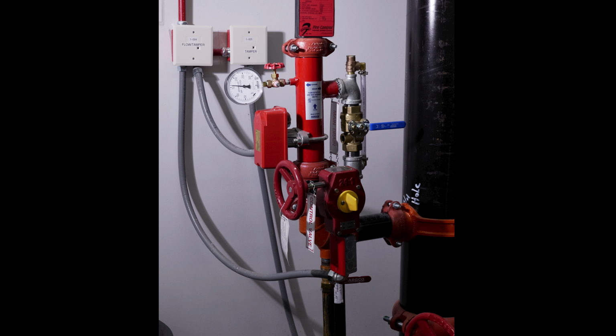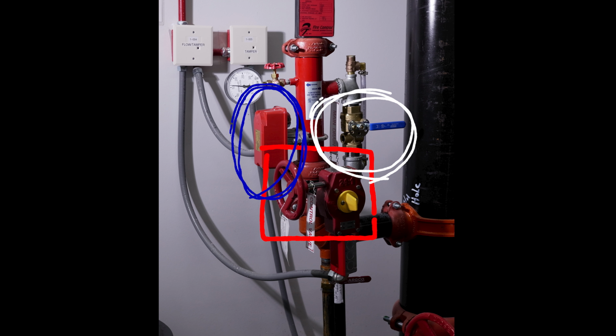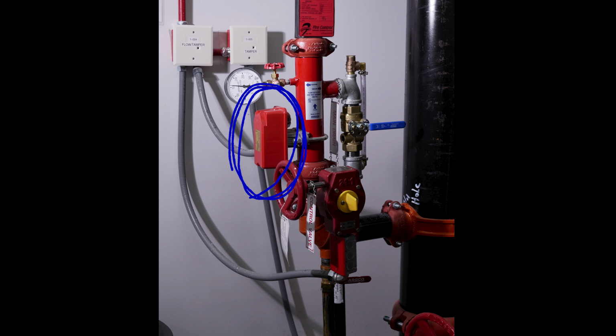The riser for this system is the simplest type, consisting of a main control valve, a combination main drain inspector's test valve, and a water flow switch to sense water movement in the pipe. The combination main drain inspector's test valve serves two functions, like the name states. By turning the handle in one direction, it operates as the system main drain and rapidly drains the system. Turning the handle in the other direction allows water to flow through a specifically sized orifice to simulate a single sprinkler head being open, which tests the operation of the flow switch and alarm system.